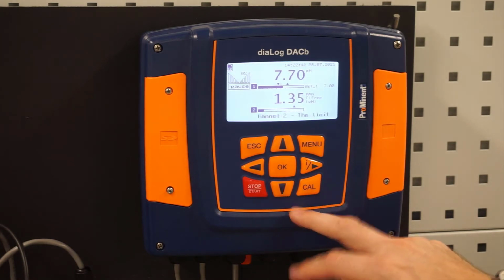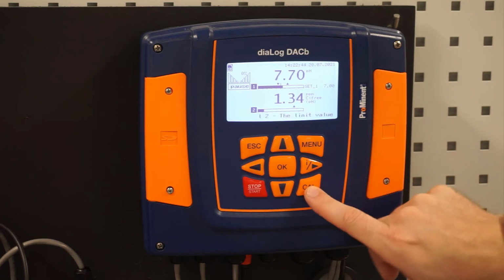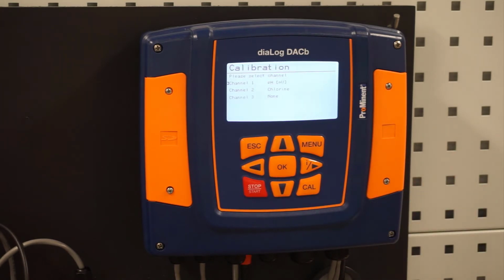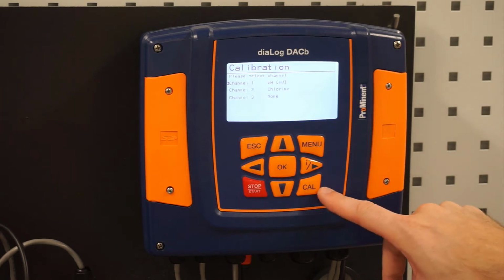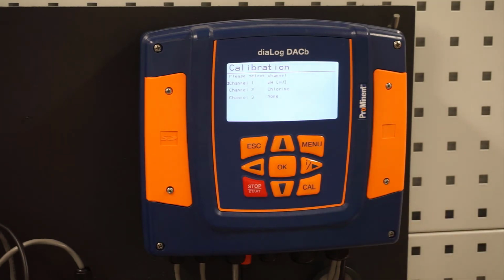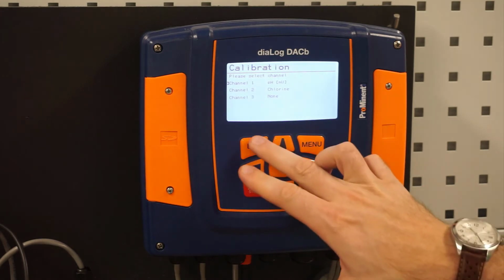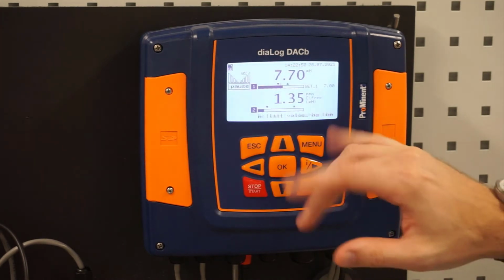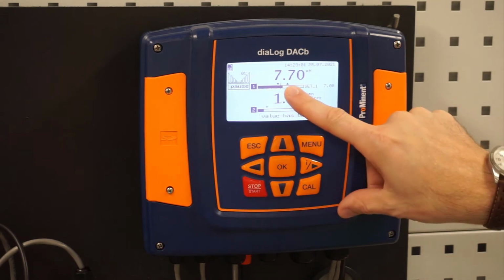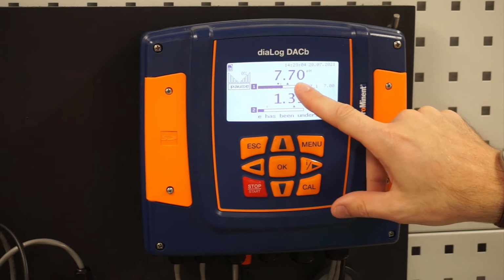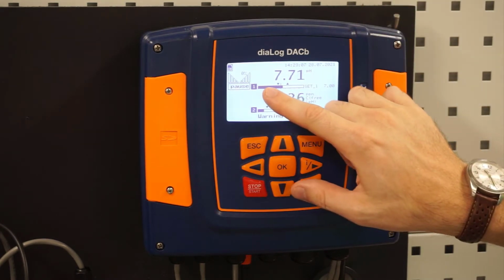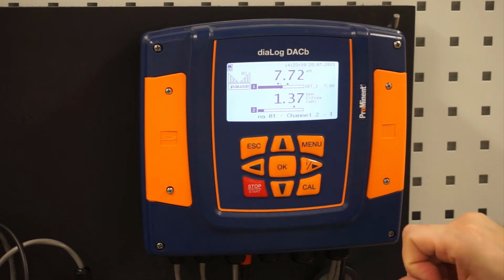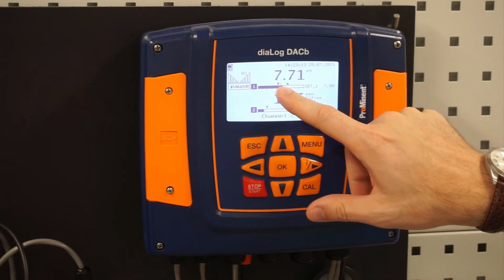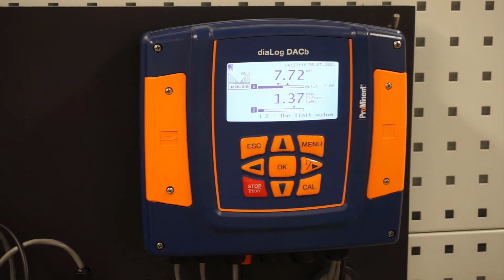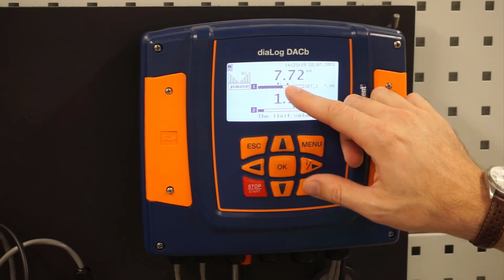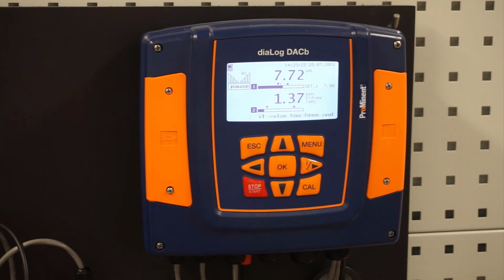Next to that, we have our down arrow key, and then we have a calibration key, which is a quick button that gets us to do calibrations. Once you have this controller set up, that's probably the most commonly used thing in here, the calibration of it. We will talk about that last. Going to hit the escape key. If we look up here, you can see on channel 1, we have our pH. So currently our pH is reading 7.70. Underneath that, that black bar represents that 7.72. The up and down arrows are our limits, so that if our pH went above this arrow or below that arrow, it would give us an alarm.